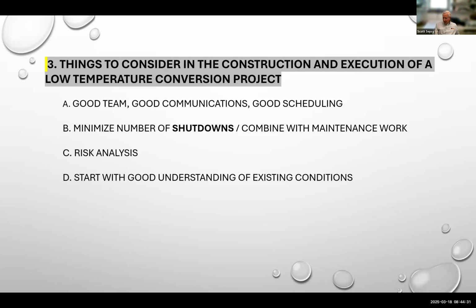Shutdowns: you have to coordinate with the building occupants. There'll likely be many shutdowns of electrical and control panels to add or change pumps or air units to replace coils. So you have to find a schedule everybody can live with. Shutdowns can be combined with maintenance testing and can be very useful. While you're replacing a preheat coil, install new humidifiers or work on electrical panels, change filters, replace lighting, verify sensors are working, install control program updates, clean airflow stations. There will also be work and traffic in hallways and occupied rooms, and these disruptions have to be socialized early in the project. Hold contingencies of money for off-hour work to address these issues. And if you're changing outside utilities, you'll need good communications with a host of other interested parties like neighbors, public safety, parking, and transportation.